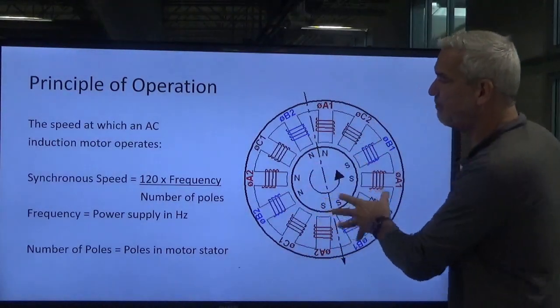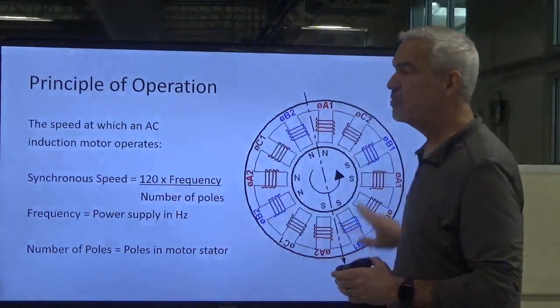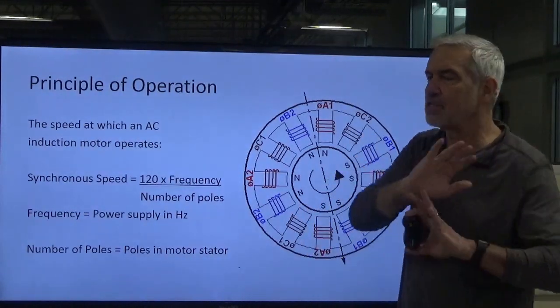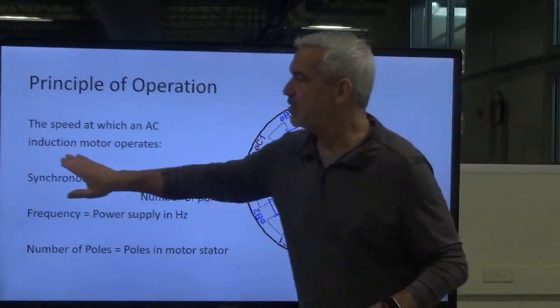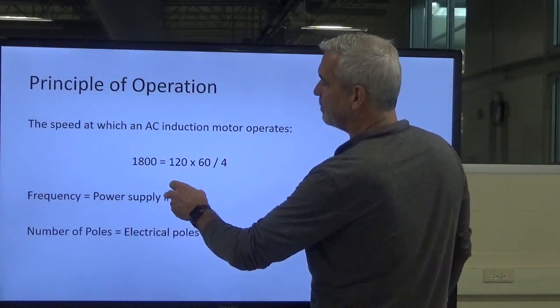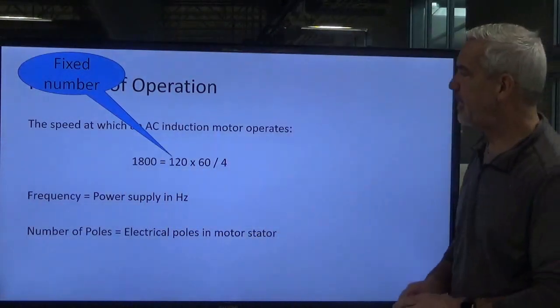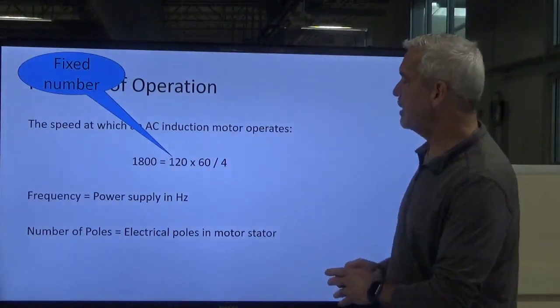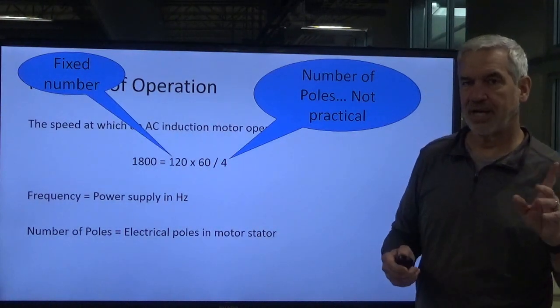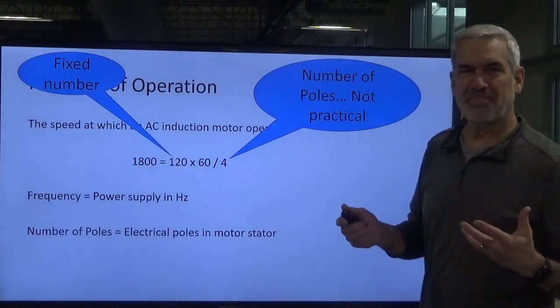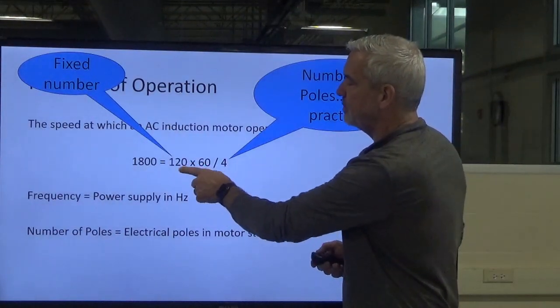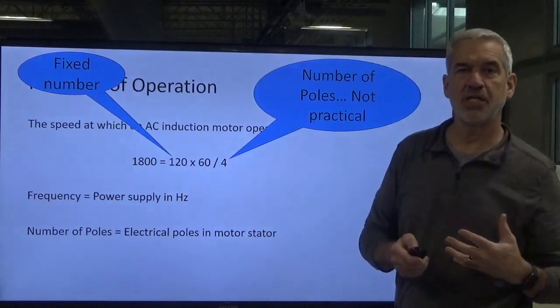We can't vary the incoming frequency, but we can control the outgoing frequency to the motor. Synchronous speed is the speed at which the rotating magnetic field is going around. The 120 here is a fixed number that stays in our formula. The 60 hertz stays consistent from our power company. And the number of poles, as I said earlier, is not practical to change. This is the formula: take the fixed number 120, multiply it by your frequency and divide by the number of poles in your motor. Most motors in the U.S. are four pole and run about 1,800 RPMs.